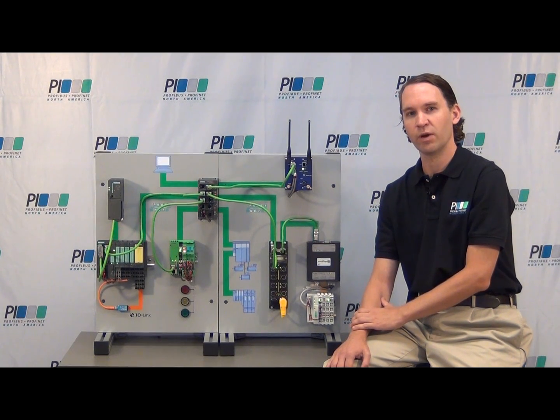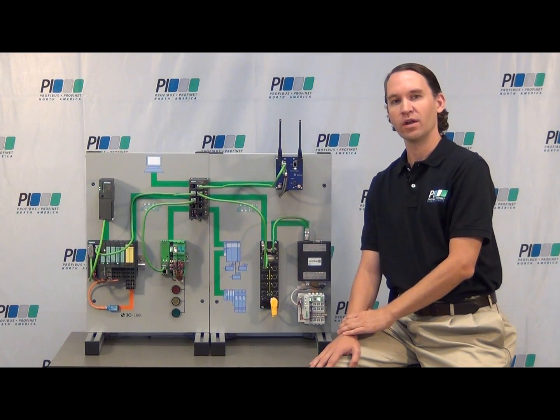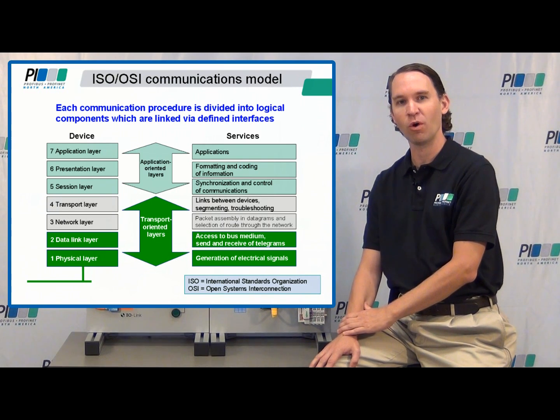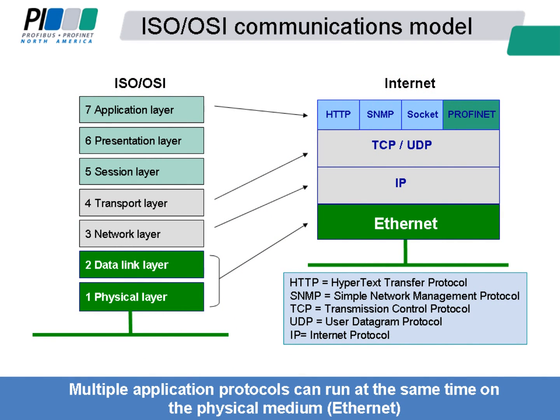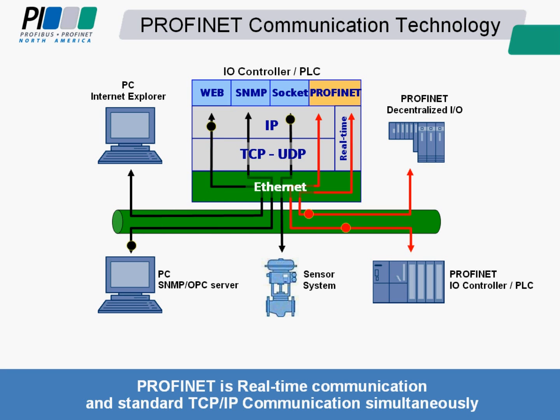Now I would like to talk about some general networking basics and how Profinet and Ethernet fit together. We cannot talk about networking and communications without mentioning the ISO OSI model. This is the original seven-layer model developed to show the different parts of the communication stack. It is up to the designers of a protocol to implement what layers and networks may be used for the communications in the model, and this really depends on the requirements for the protocol and the necessary applications. Profinet covers all application requirements for industrial automation by making effective use of the model. The example illustrates how Profinet allows office and real-time communication simultaneously. This is because Profinet supports both Ethernet and TCP/IP. When discussing Ethernet in the factory environment, we would like to state that the term industrial Ethernet is often used, which has the same communication characteristics as Ethernet, but uses more ruggedized equipment and cables.